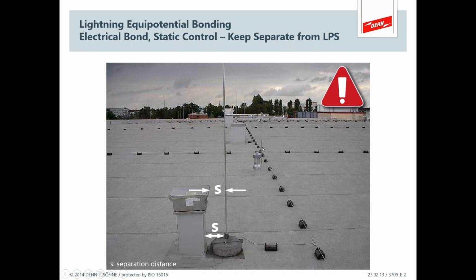And then when you're going past this vent stack, it's all right that you bond to it because it's dead metal that isn't doing anything else. So that's the purpose of lightning equipotential bonding: to either electrically bond it or keep it separate. There are other reasons for bonding, of course. You have to have bonded metal for grounding, for electrical safety, and you have to have bonded metal for static control, but don't bond it to your lightning system unless you really want to. And that's the point. Pay attention to it. Don't disregard it.